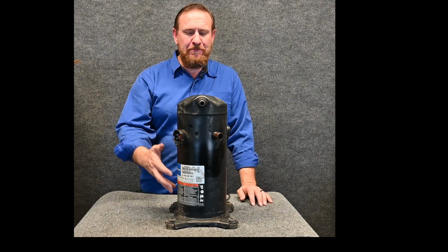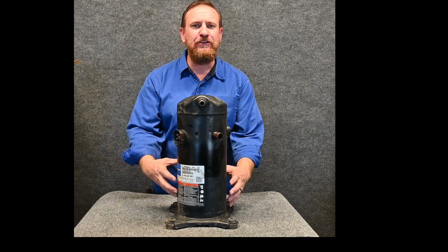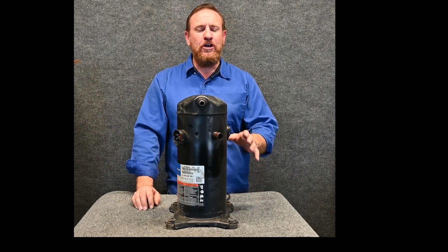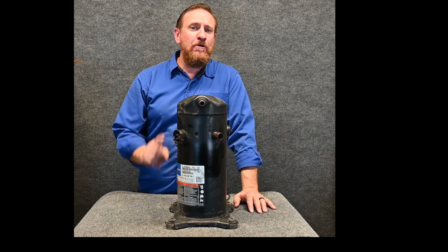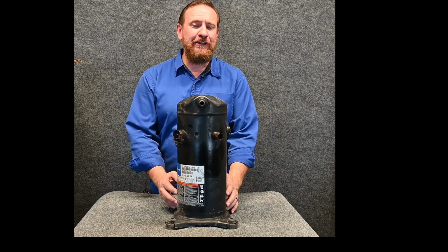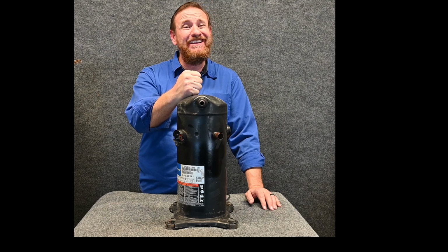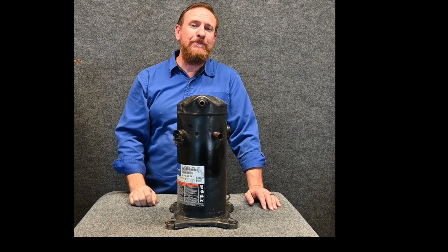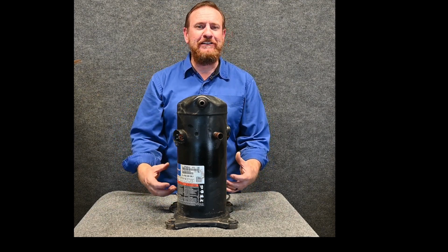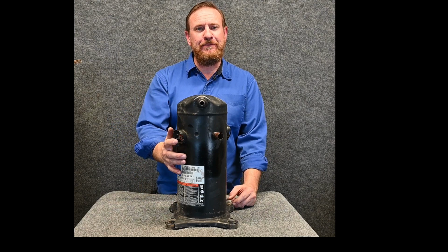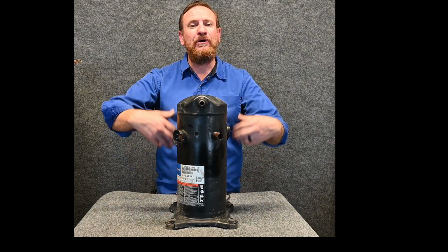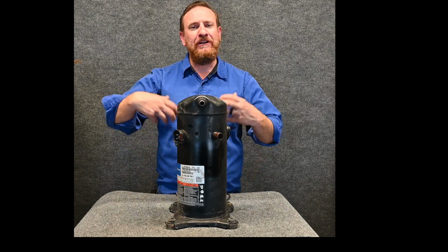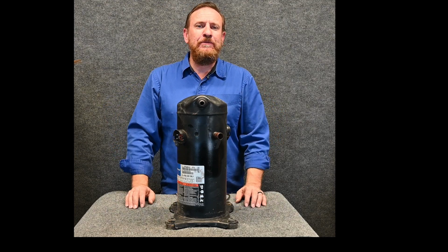And as the refrigerant migrates to the compressor, it soaks in with the oil. And that causes two problems. When this compressor does start back up, we have issue number one. We now have liquid refrigerant going into our vapor pump, and something's going to break. And problem number two, as the refrigerant mixes with the oil and we start our vapor pump up, that refrigerant starts to boil out of the oil. As it starts to boil out of the oil, it starts to become foam.